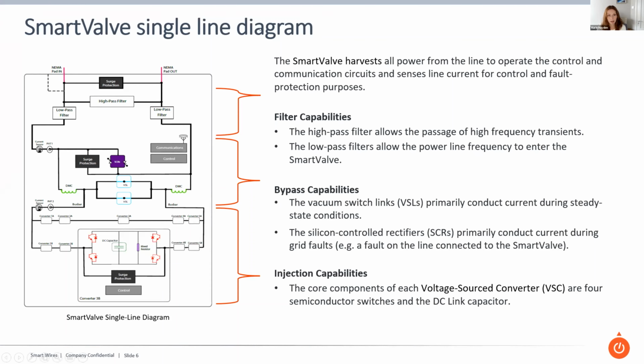So we're talking about faults maybe out on the grid where all of a sudden the current coming into the line increases very dramatically. It's detected by our current sensors, and they fire the silicon controlled rectifiers, which are designed to handle tens of thousands of amps. And these devices then fire for as long as the fault is on the system, up to about 1.5 seconds, at which stage the power system protection will have cleared the fault. And at the same time as these are firing, we also close up these VSLs. So we have a second path for the fault current through the VSLs. So that's really the fundamental power electronics components of the device, the SCRs and the IGBTs.